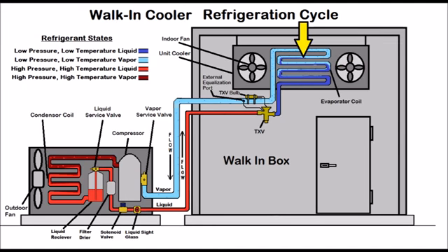Once the refrigerant's a complete vapor, it ends up increasing in temperature until it comes out of the evaporator coil. So the temperature difference between where it turns into a complete vapor from the saturated state and where it comes out of the evaporator coil, that's called the superheat. And that's why you have the thermostatic expansion bulb and the external equalization port mounted on the suction line right after the evaporator coil. That thermostatic expansion valve is actually reading the superheat, and it's trying to maintain the superheat.